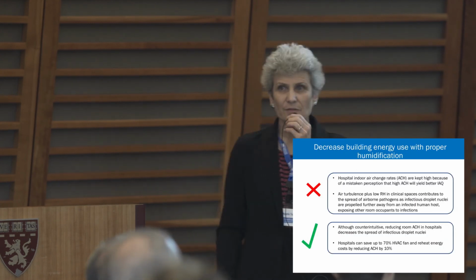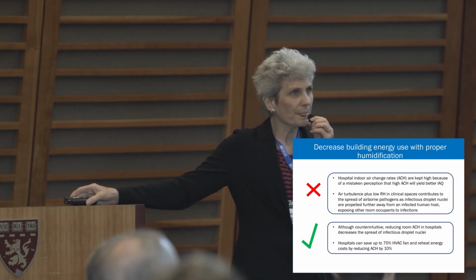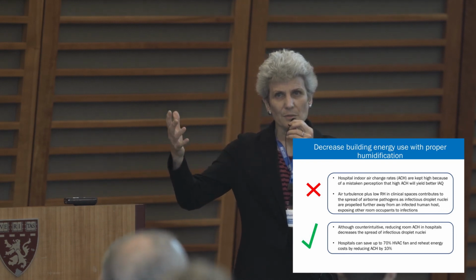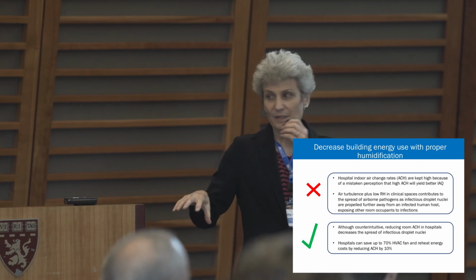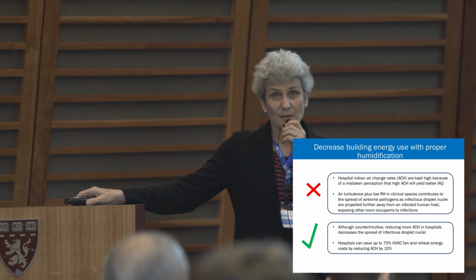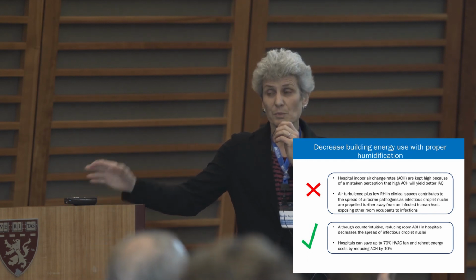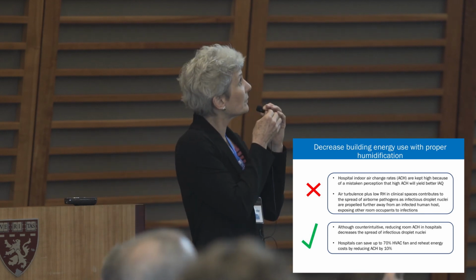So another interesting factor is, we spend a lot of energy on room air changes in hospitals. But there's studies now that show that if you properly humidify your hospital air, you can turn down the room air changes. So for example, in an OR, where you have 20 room air changes an hour, if you could decrease your room air changes and save the energy from that, you'll be moving in the right direction, both in terms of infection control and energy sustainability.